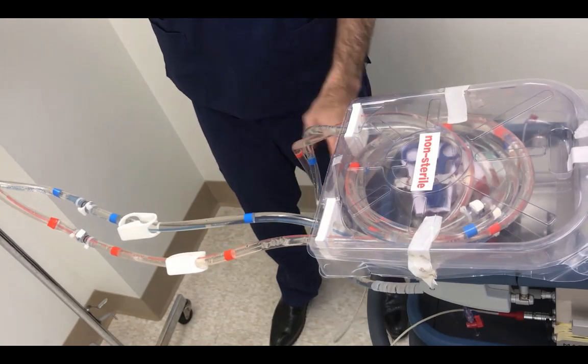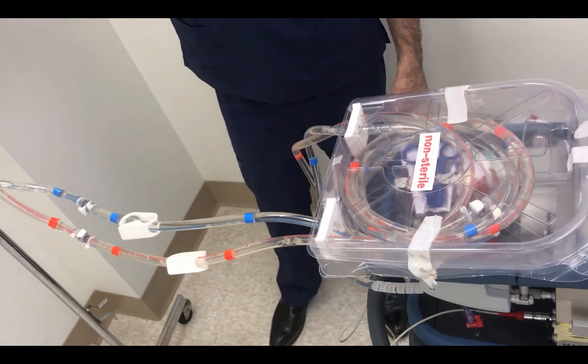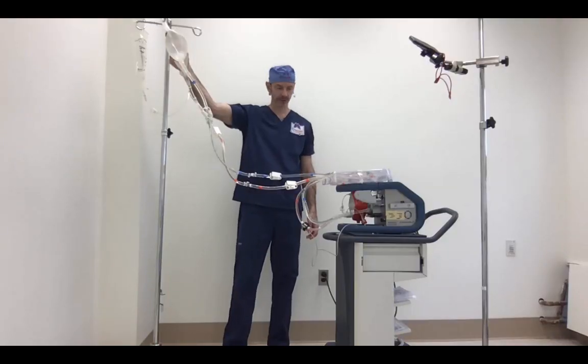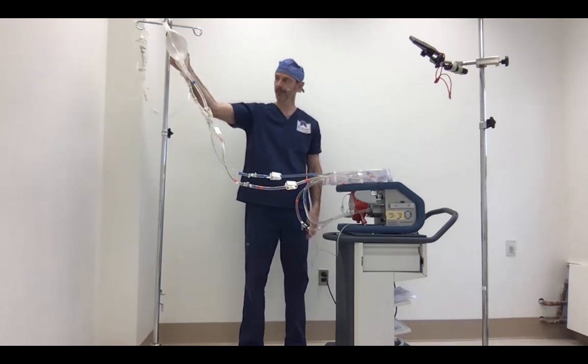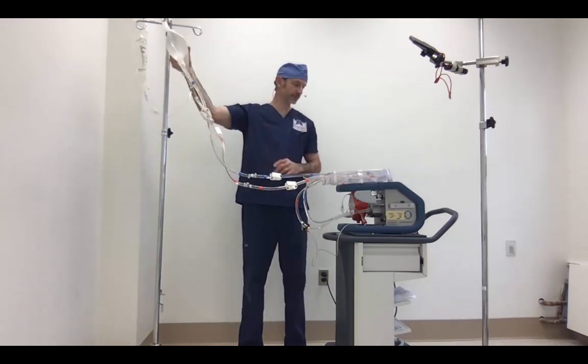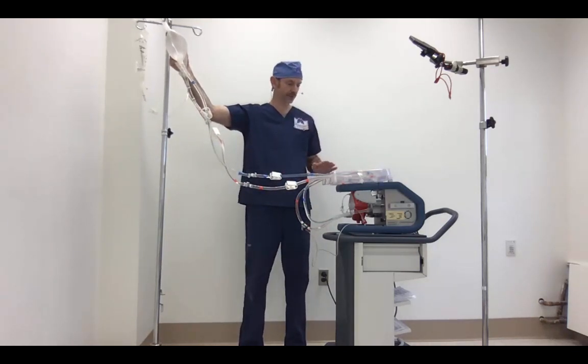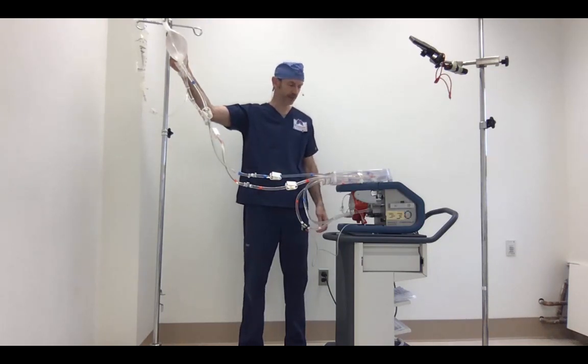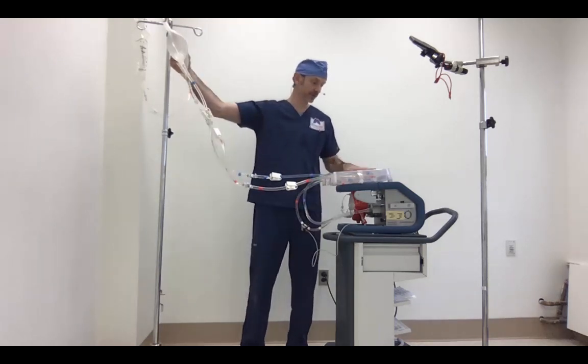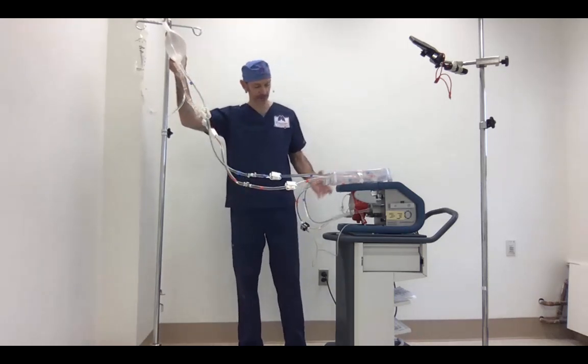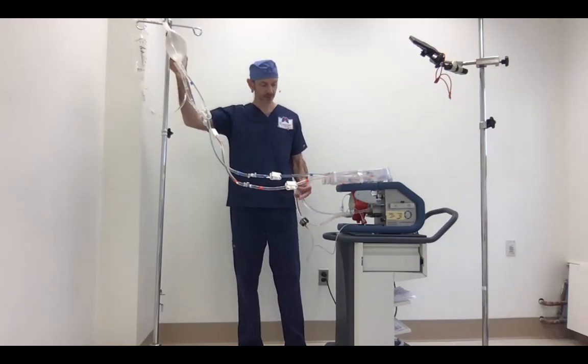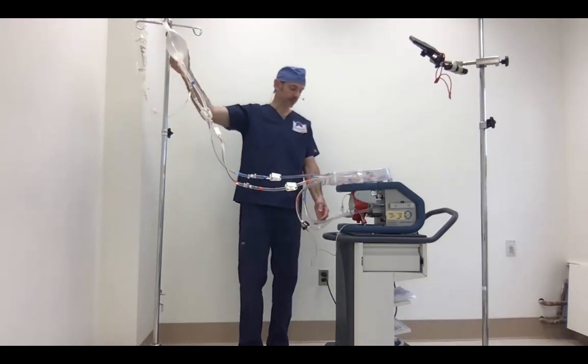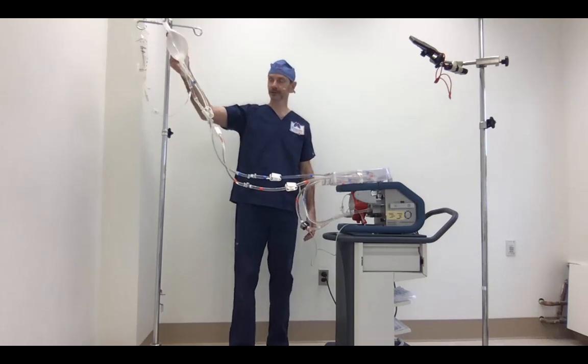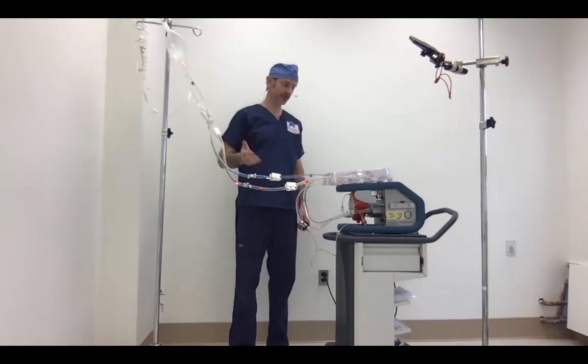Now I'm squeezing this bag. But you shouldn't have to do that. In a brand new clean system with 30 inches of height and 2 liters of fluid, a circuit that's never been primed, this happens seamlessly without any effort on your part. As a perfusionist, we often feel like we need to reach out there and pat this box and get things to move along, but the truth is, on a sterile, clean Cardiohelp system, you pop these clamps, it primes itself.